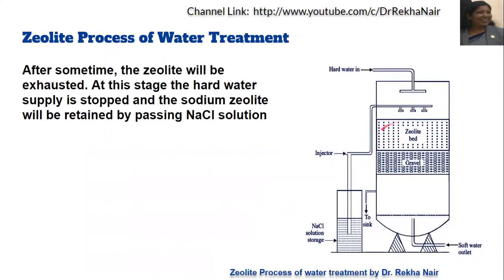After some time, the zeolite becomes exhausted because all the sodium zeolite is converted into calcium and magnesium zeolite. At this stage, the hard water supply is stopped, as the bed has been completely converted into calcium and magnesium zeolite. The softening capacity of the zeolite bed becomes lesser compared to the initial stage, so we need to regenerate it and get the sodium zeolite back.